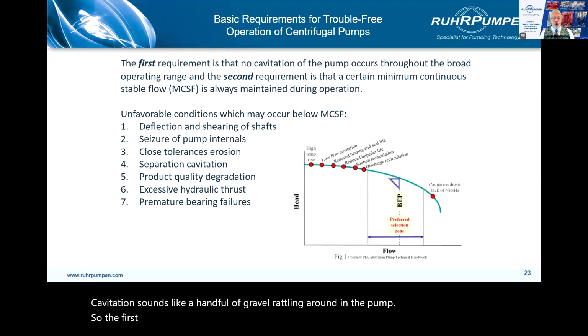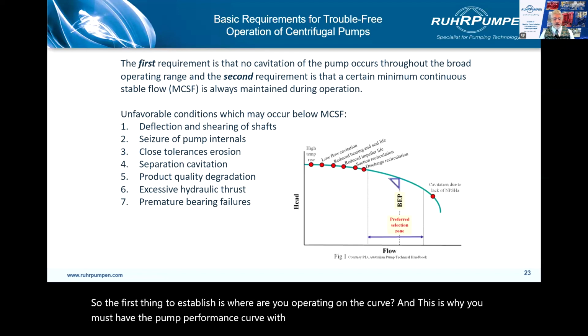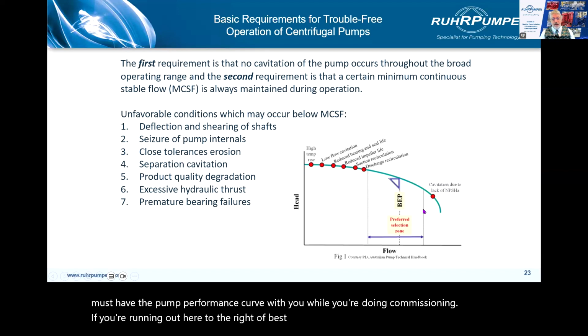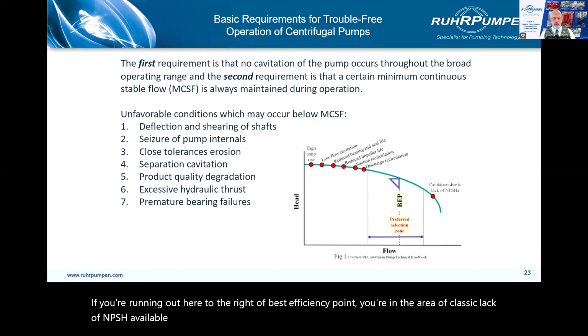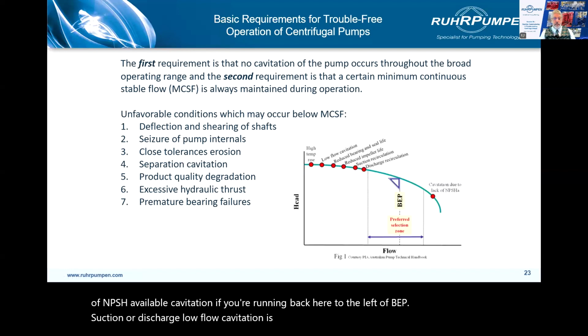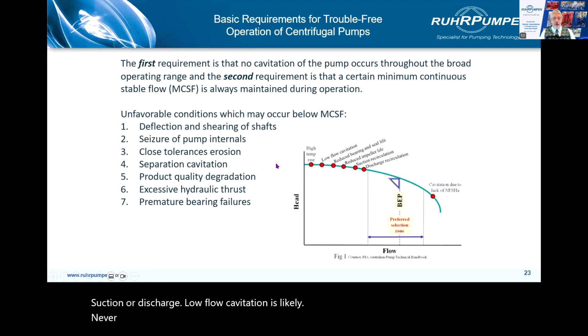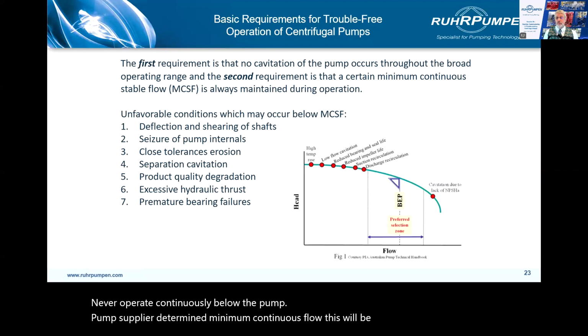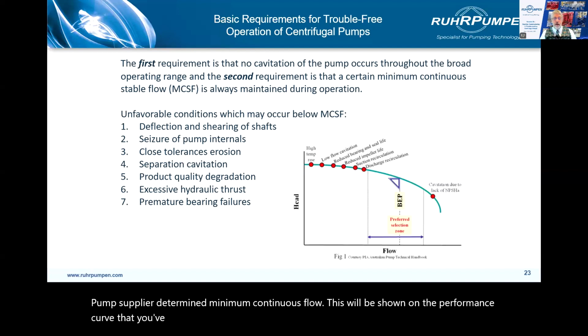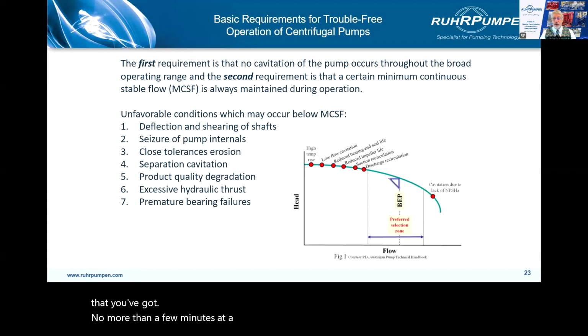So the first thing to establish is where are you operating on the curve? And this is why you must have the pump performance curve with you while you're doing commissioning. If you're running out here to the right of best efficiency point, you're in an area of classic lack of NPSH available cavitation. If you're running back here to the left of BEP, suction or discharge low flow cavitation is likely. Never operate continuously below the pump supplier determined minimum continuous flow. This will be shown on the performance curve that you've got. No more than a few minutes at a time, followed by a return to a higher flow.